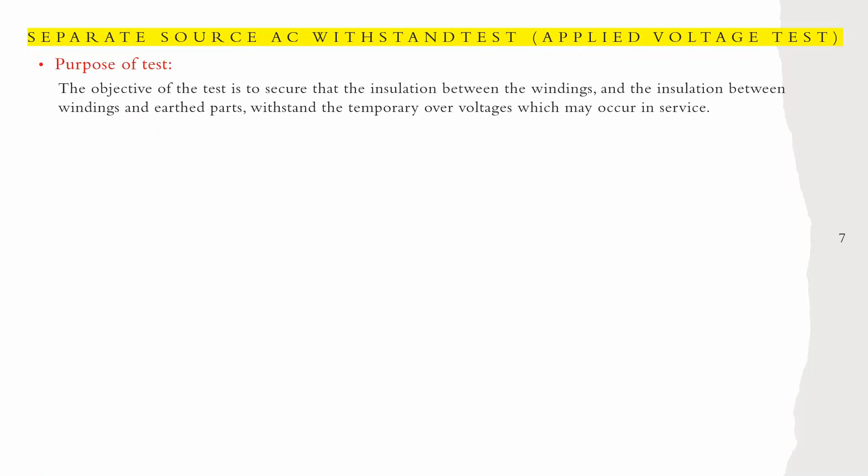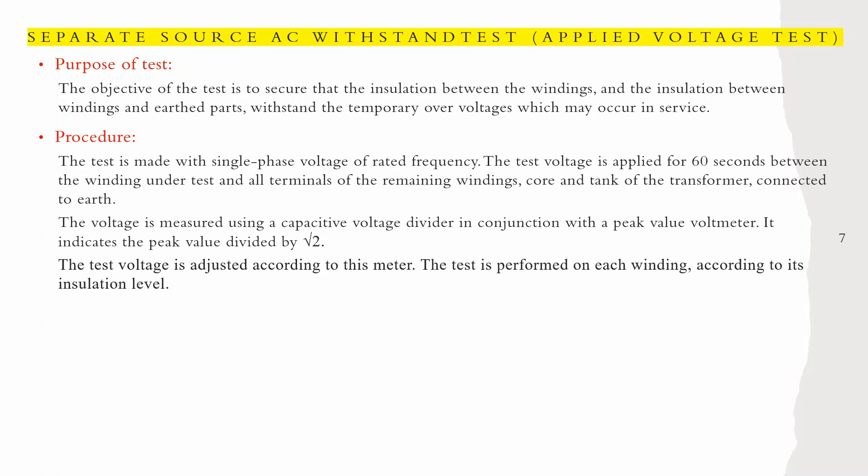The next test is the separate source AC withstand test, also called the applied voltage test. The purpose is to verify that the insulation between the winding and earth parts can withstand temporary overvoltages that may occur in service. The procedure: a single-phase voltage at rated frequency is applied for 60 seconds between the winding under test and all terminals of the remaining windings, core, and tank, connected to earth. The voltage is measured using a capacitive voltage divider in conjunction with a peak voltmeter, indicating the peak value divided by the square root of 2.